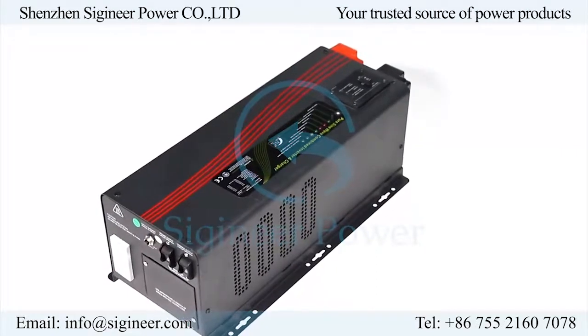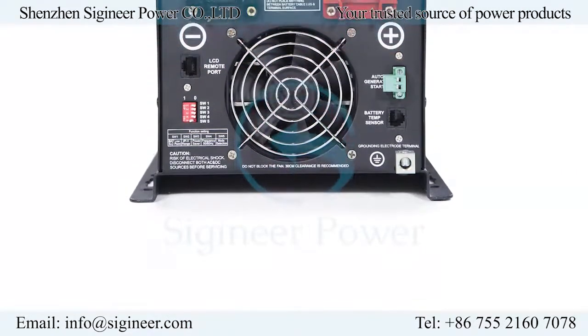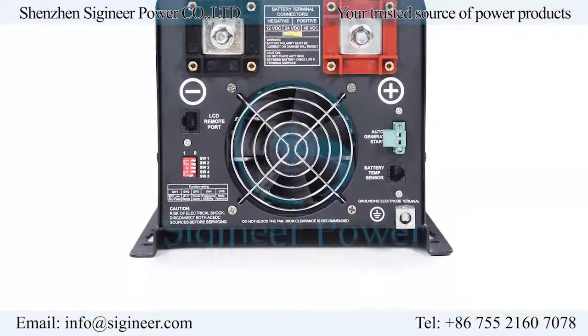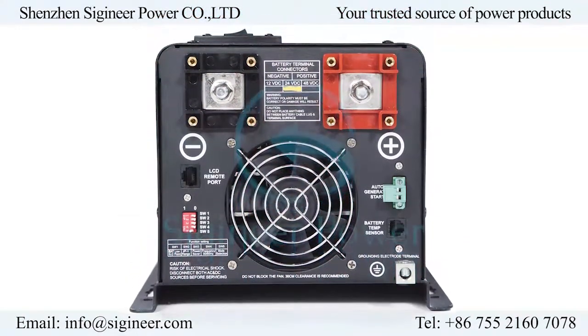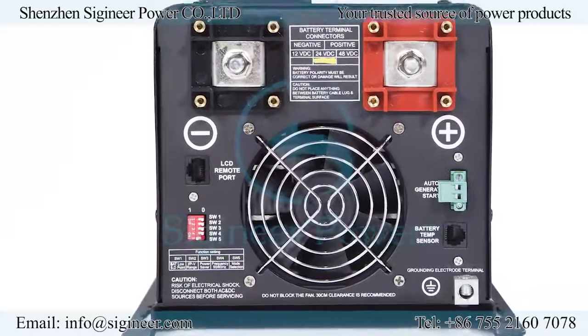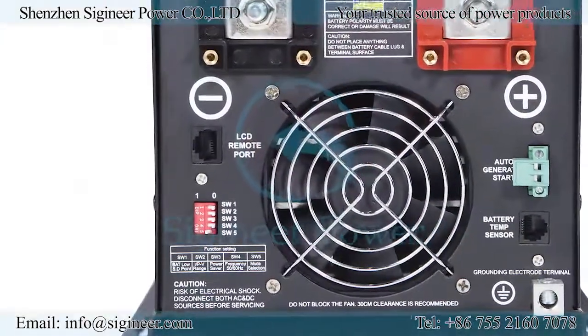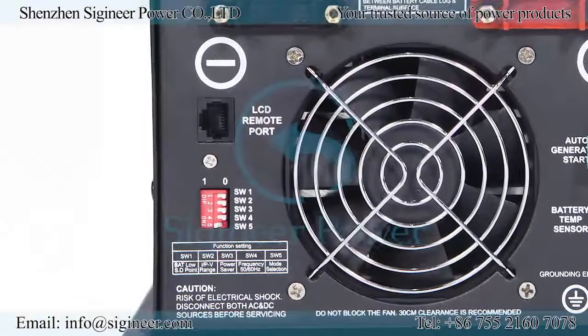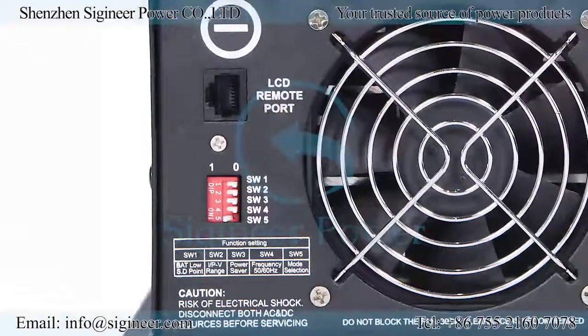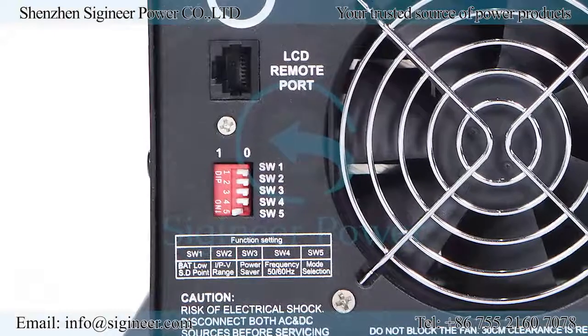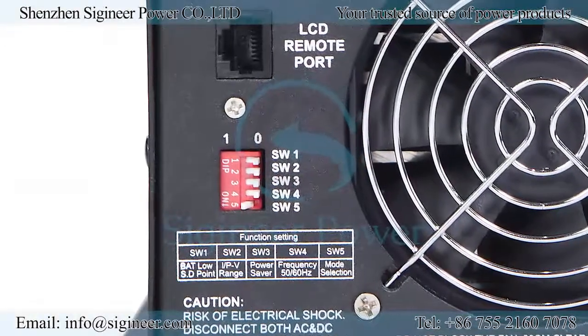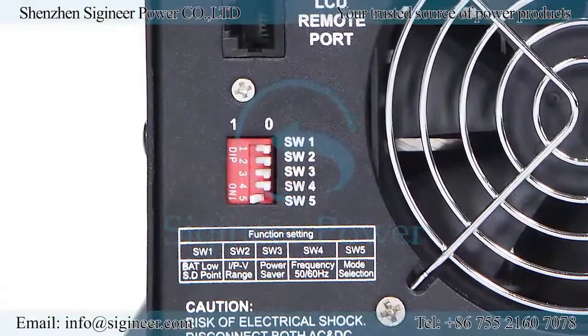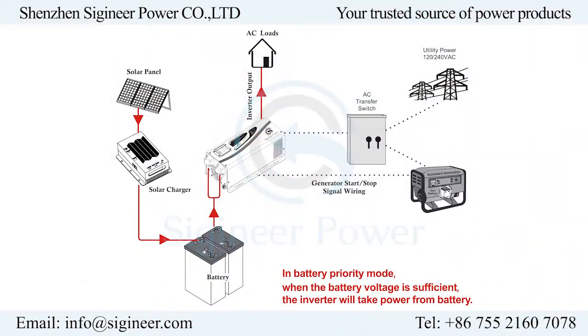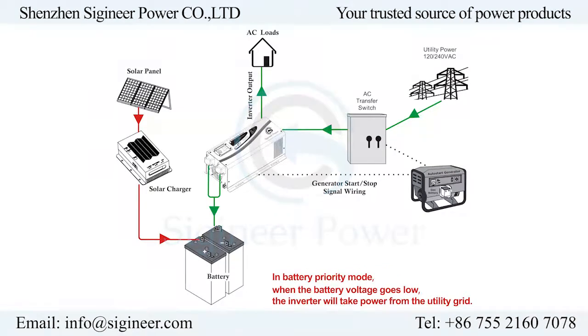There are some exclusive features only available from Sigineer Power, such as DIP switches, auto generator start, and battery temperature sensing. The DIP switches are near the DC terminals of the inverter. They control inverter specifications, including low battery voltage shutdown, AC input voltage range, power saver mode, output frequency switch of 50 or 60 Hz, and battery priority mode. The battery priority mode prioritizes the DC over AC, which means the inverter will only switch to utility power when the battery power goes low.